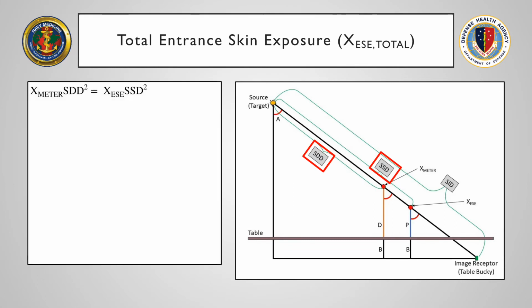Now the value we recorded on that radiation detector, I already told you, 1059 milliroentgen or 1.059 Roentgen. So to get from the detector to the source to skin distance, we need to use the inverse square law, just like we did from our CHP practice problem in the first half of this presentation.